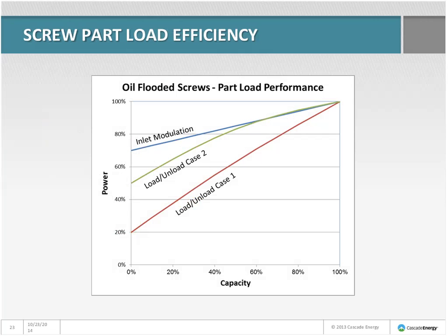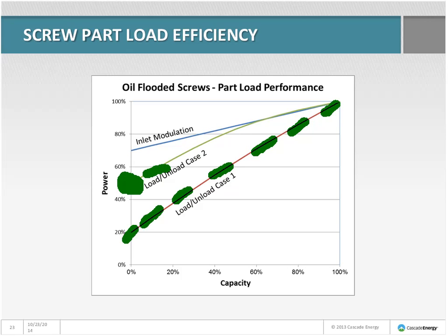With load-unload control on screw compressors, if we have a good setup and compressors that unload well, we can have a very nice part-load curve. A well-configured compressor uses about 20% power when fully unloaded. With sufficient tank volume, the part-load line is nearly straight — pretty efficient operation across a wide range. But if a compressor doesn't unload far — holding 40 or 50 PSI in the sump — it might still use 50% power even after five minutes unloaded, and with little tank volume it will cycle quickly, giving poor part-load performance.